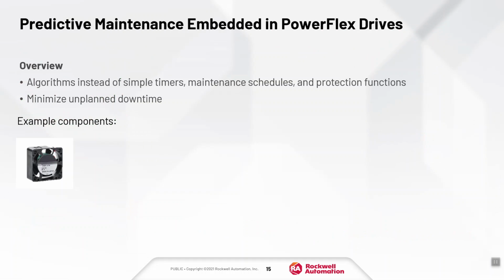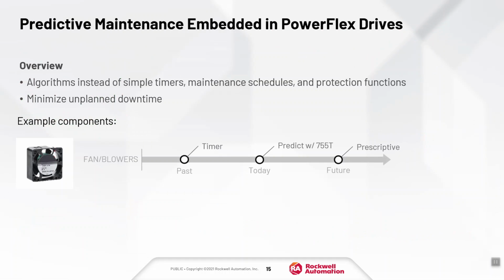Here's just a quick build of that predictive maintenance that's embedded in PowerFlex drives. So a couple of example components that we're subscribing to here. What we're able to do in this case with the fans and blowers is, in the past, we really were only monitoring a timer.